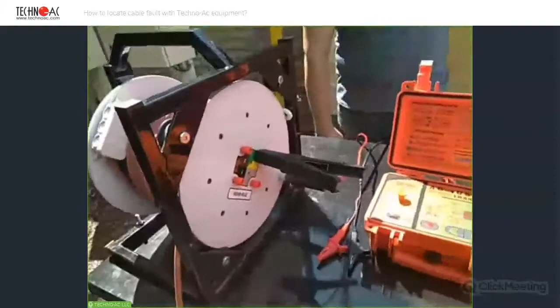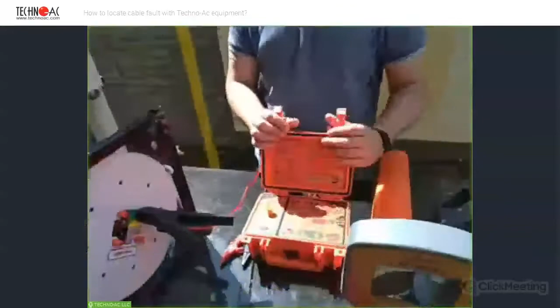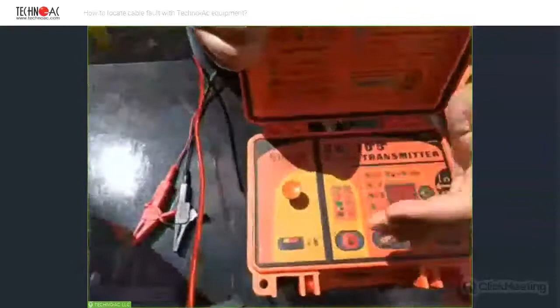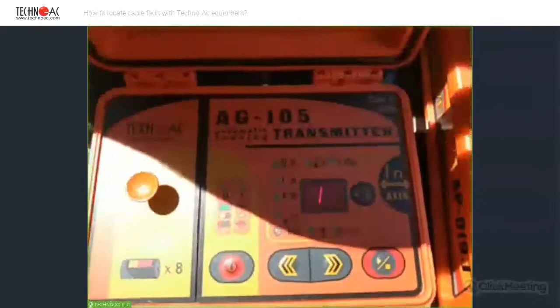I have connected the transmitter on the other side to the grounding. Don't forget to ground your transmitter. You can see my grounding stake here and the red dot. It's very important for any transmitter, I mean, for cable location, for pipe location, and even for cable fault location with electromagnetic equipment. And we will enable 8 kilohertz frequency signal. We will turn on our transmitter. I guess because of the sun, we will not be able to see the settings of the transmitter, but I will cover them with my hand so you can see the values on the screen.